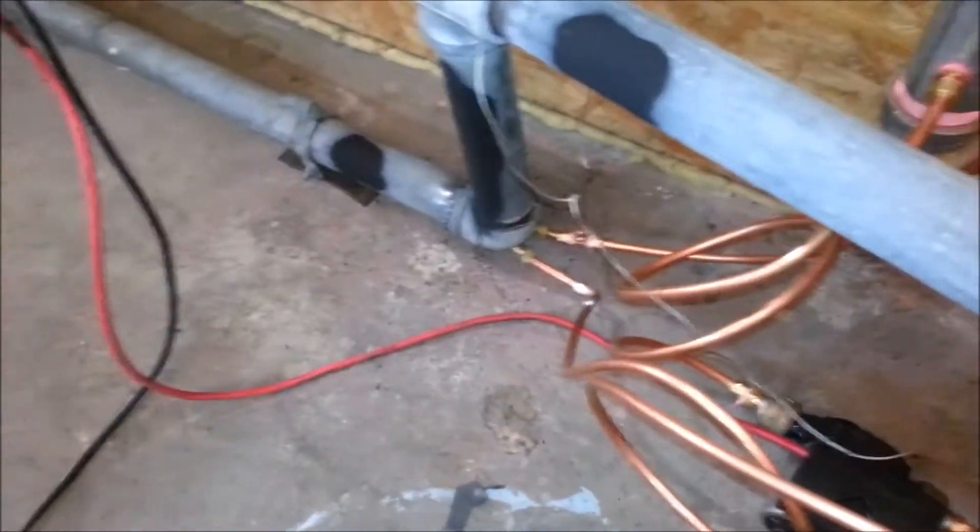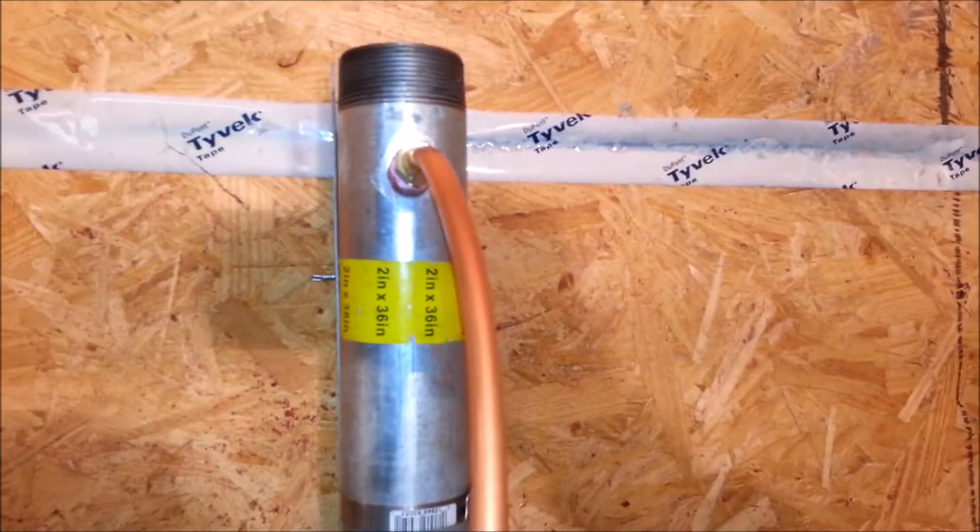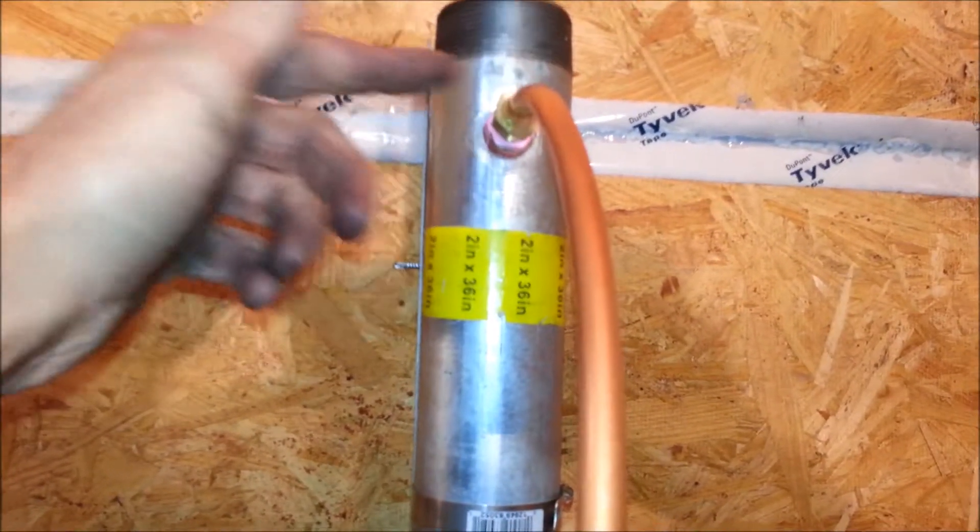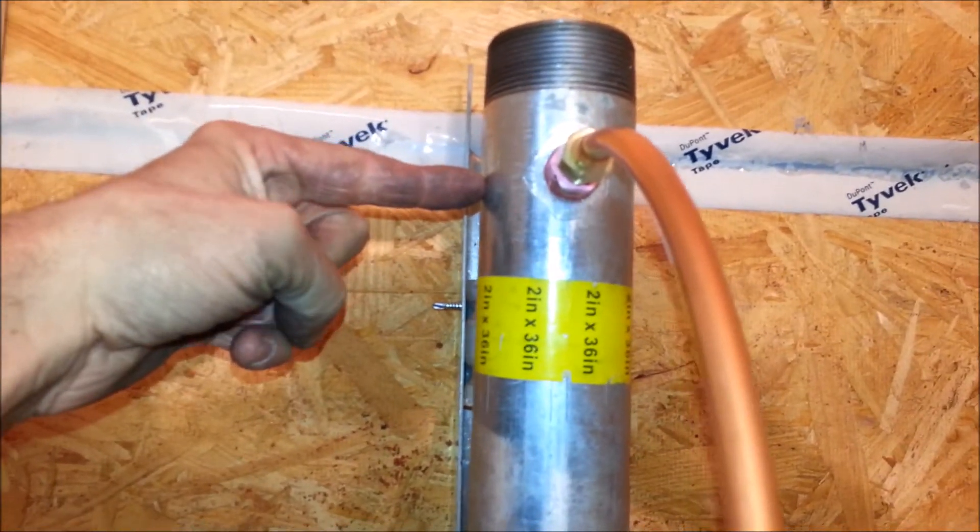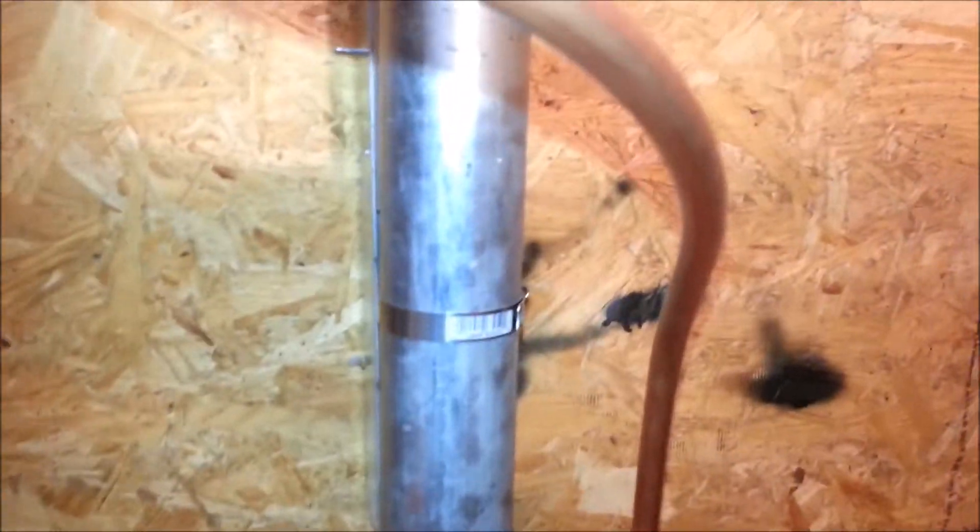This here is a mixer tank that will eventually be connected to a different radiator. Because of the flow rate differences of the heating system versus the radiator system, I would simply have another connector connected here and up here. This thing would be filled up all the way so that the radiator could pull hot water directly from one port. Any flow discrepancies would be eliminated with this tube. So even though I have a low flow rate in my heat system with this small coil, I can tie into this in a proper way to give us a more desired effect.